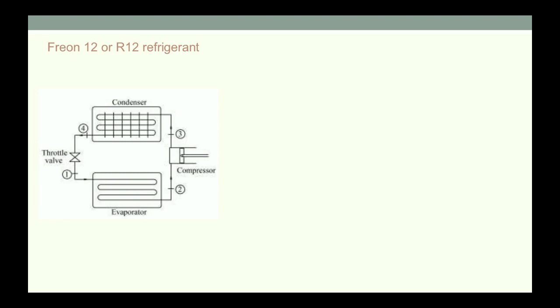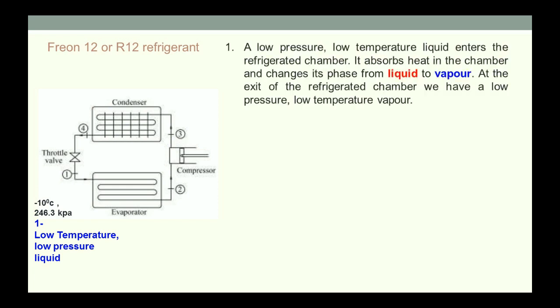After knowing the components of the refrigerator, we try to understand how it works. The refrigerant entering the evaporator will be at low temperature and low pressure liquid, normally minus 10 degrees centigrade and 246.3 kilopascal. This liquid refrigerant, when it enters the evaporator, absorbs heat from the surroundings and becomes vapor. In this way, the refrigerant coming out of the evaporator will be low temperature, low pressure vapor.